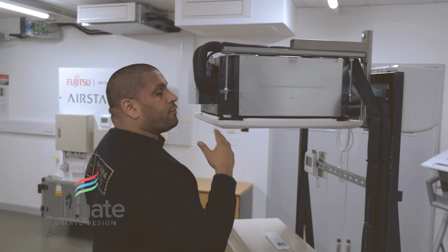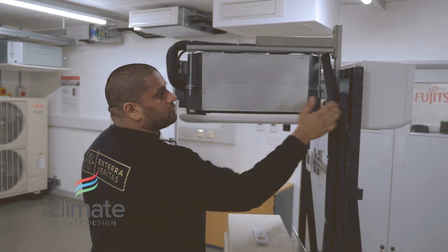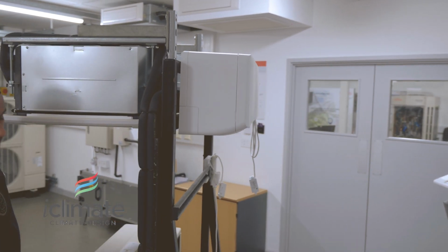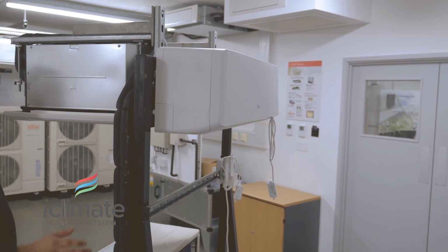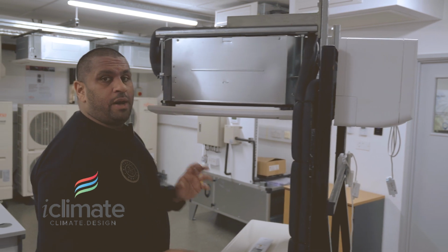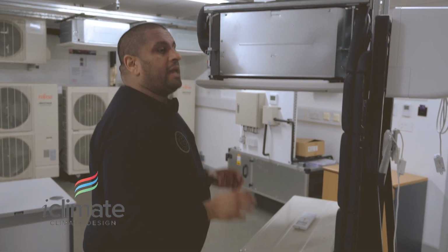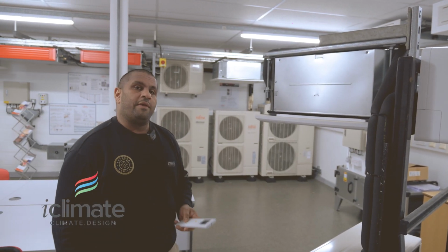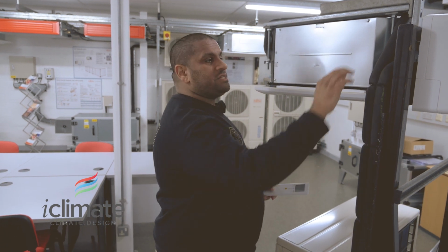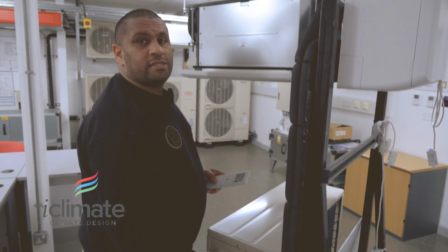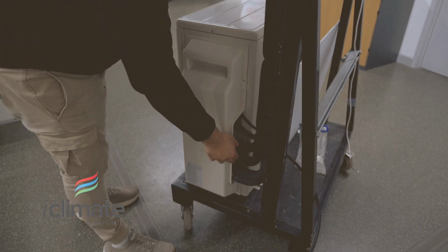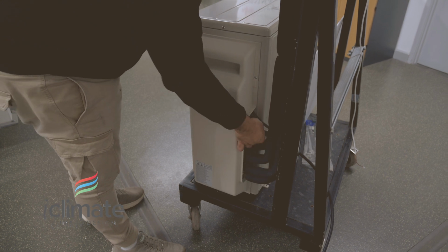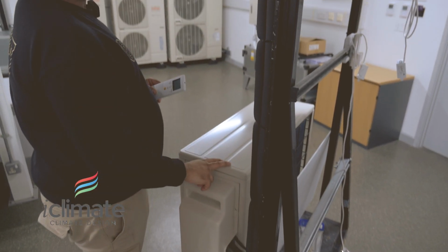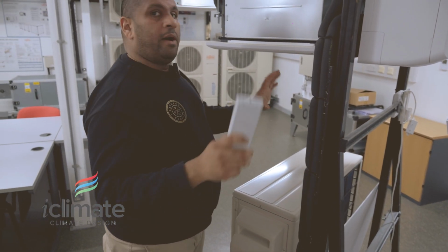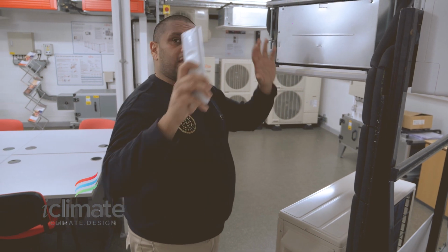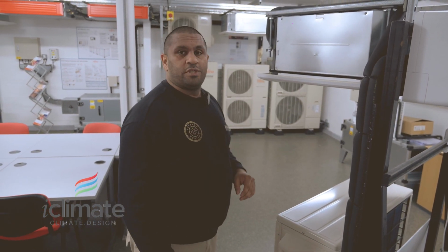As you can see here, we can have a different arrangement of indoor units. So you can have a compact ceiling cassette and also a small compact wall unit fed with the pipework back to the condenser. One key thing to note on multi-installations is there'll be a set of pipes and interconnecting services between the condenser and every indoor unit in your property. The key thing to remember about the multi-system arrangement is every indoor unit will need its associated pipework and interconnecting cabling running directly back to the multi-condensing unit you can see here. So we have 2 sets of pipework here, one feeding the wall, one feeding the compact, with the associated interconnecting cables running all the way from the outdoor to the indoor. So in your house and property, we'll need to plan the pipework. So whatever the multi-condenser is, we can aesthetically install it so it suits the outside while also minimal disruption inside.